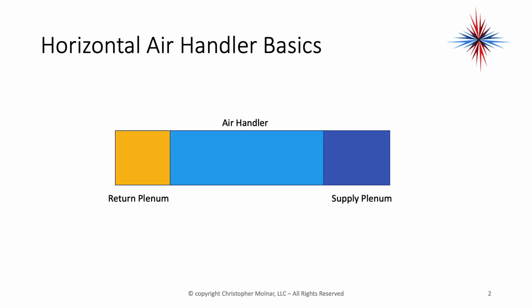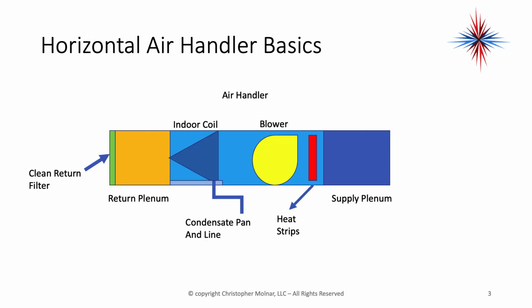To make sure we're all on the same page, let's talk about some air handler basics. If we're looking at a horizontal air handler, that's one that might be installed in an attic or a crawl space on its side, we have a return plenum, we have the air handler, and we have the supply plenum. All the ductwork is connected to either side of this. In the return plenum someplace or on the return side of the ductwork, we have an air filter. Then we go into an indoor coil. Then we have our blower. We might have heat strips or some other means of heating. And then we have a supply plenum.